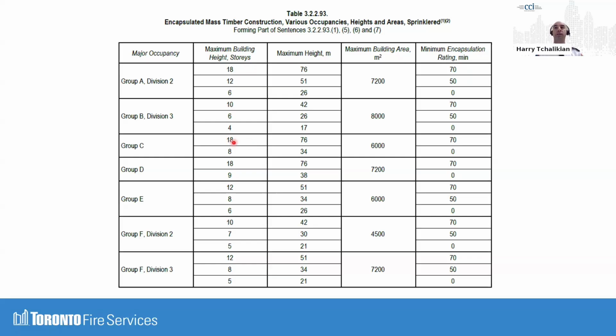And so for group C, the residential occupancies, this is you guys, it's divided into 2. So maximum building height in stories, 8 stories, and then you can have a 0 rated encapsulation. And if you go above 8 stories, you need 70 minutes of encapsulation, meaning that the drywall would have to withstand for 70 minutes. And then this column here where my laser pointer is, that's the maximum building area, which is the bird's eye view footprint of the building.